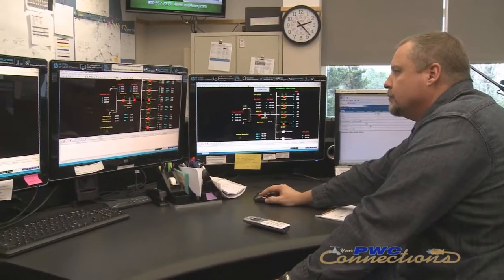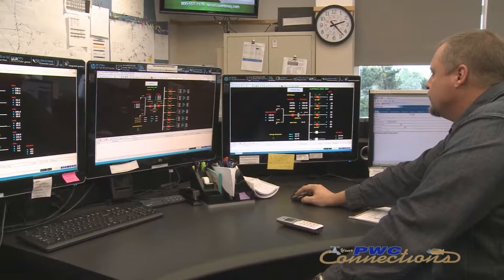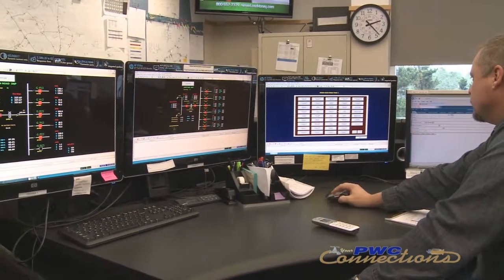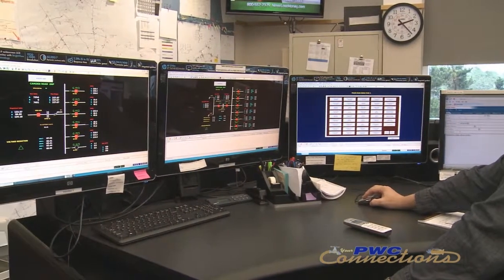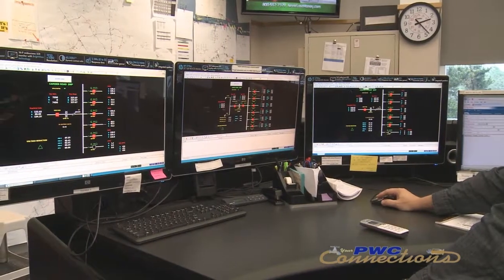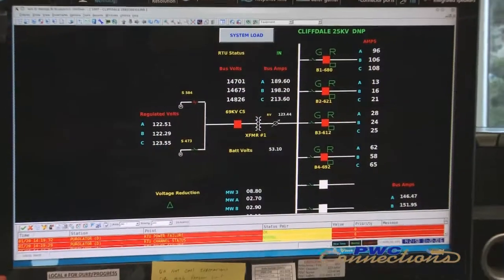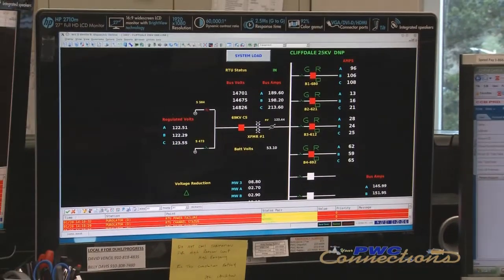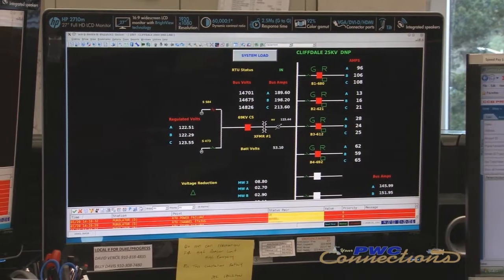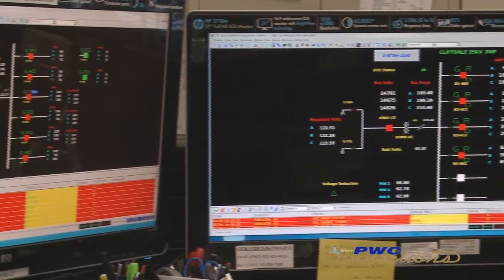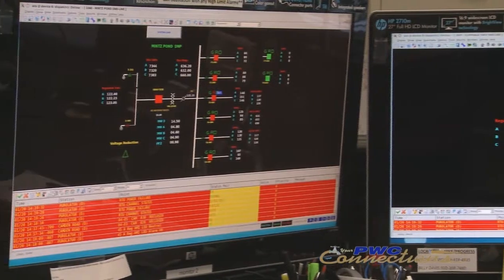But substations play a key role in providing power throughout America. At the Fayetteville PWC, we use a computer system, and in a substation world we call it supervisory control and data acquisition. It's a big word, so we've shortened it to SCADA. That system monitors all our equipment and gives us alarms if an event happens in a piece of equipment, and we're able to monitor the power flow and actually control breakers by opening and closing them.